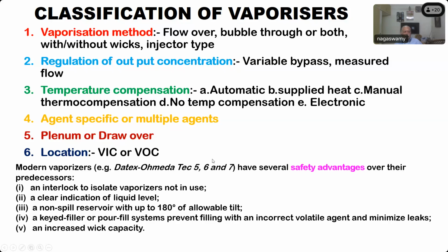Many vaporizers have a transparent glass portion, and there are markings seen as full, half, or empty, or various measures in milliliters also. What is that area through which you see whether the vaporizer is filled adequately or it is getting emptied? A clear glass portion. It is called the sighting glass. Sighting glass. Okay, you sight the level of the liquid to find out whether you need to refill it or not. And there are non-spill mechanisms.